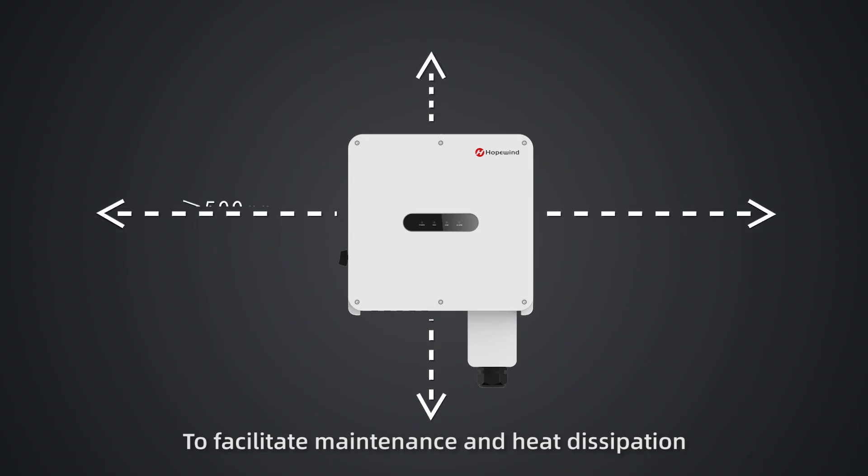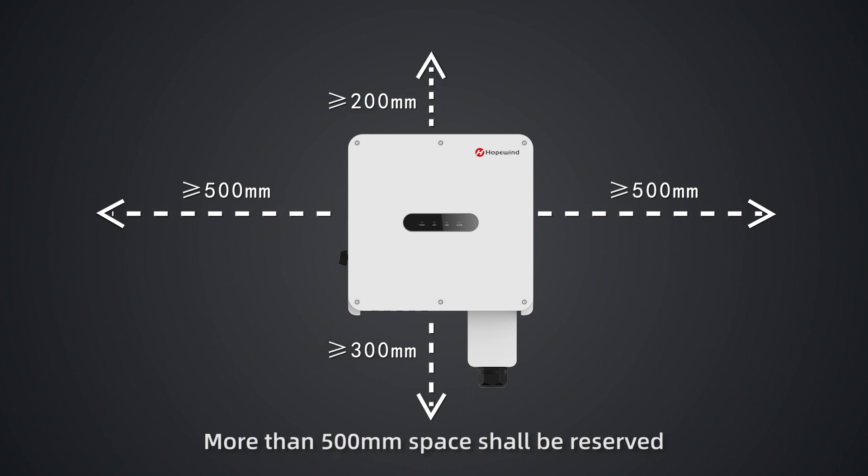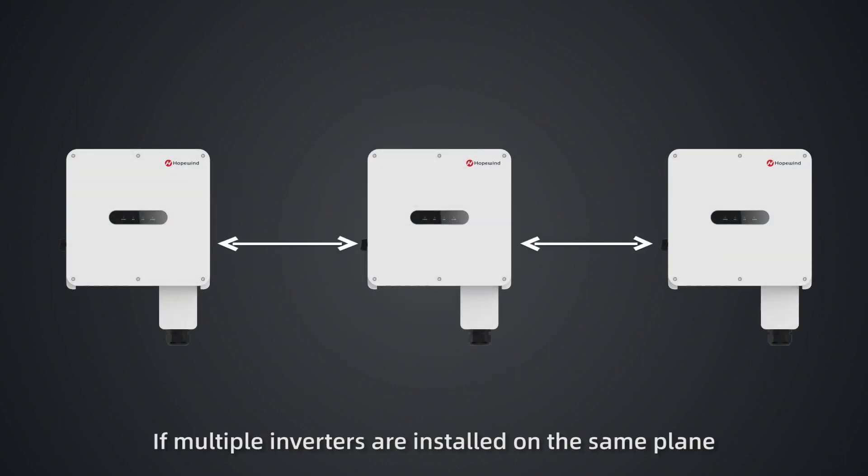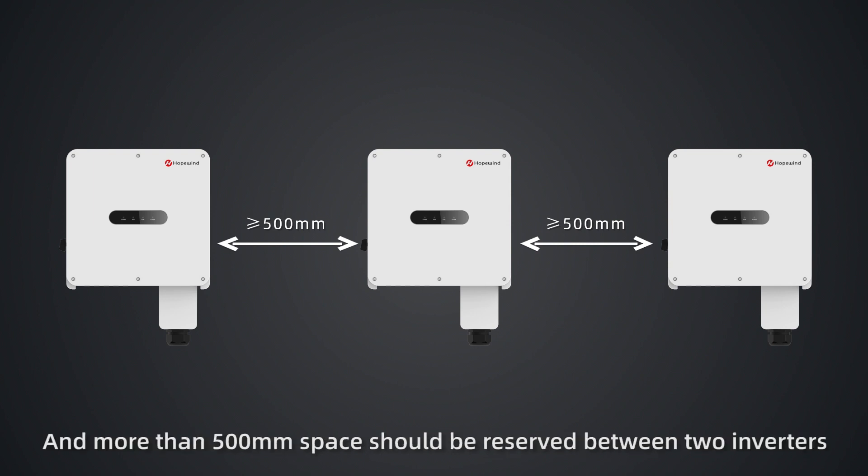To facilitate maintenance and heat dissipation, more than 500mm space shall be reserved on the left and right of the inverter, and at least 200mm space above, and 300mm space below the inverter. If multiple inverters are installed on the same plane, side-by-side installation is recommended, and more than 500mm space should be reserved between two inverters.